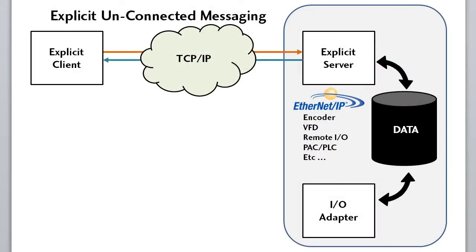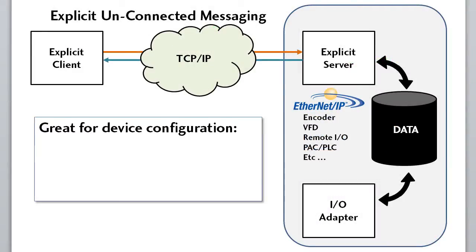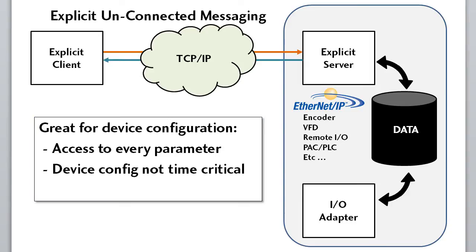Explicit unconnected messaging is typically used for setting up and configuring a device because it gives you access to every parameter in the device. Setting up the device is not time critical and you can be confident the parameter actually got to the device because it uses TCP/IP protocol which guarantees delivery of those parameters.